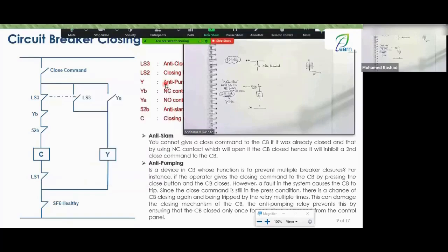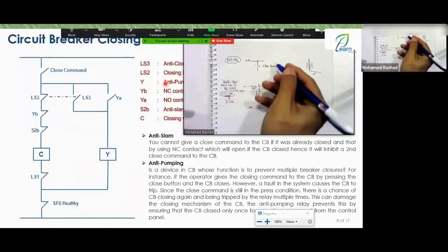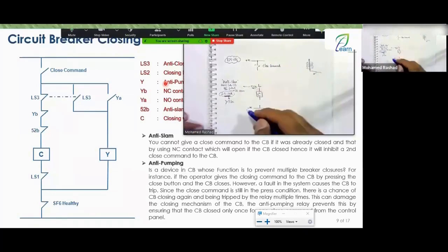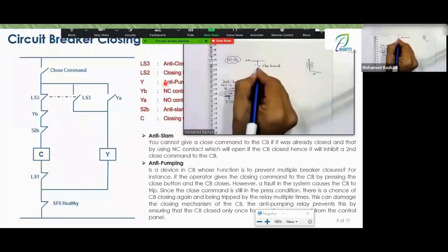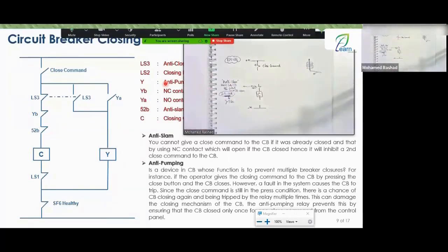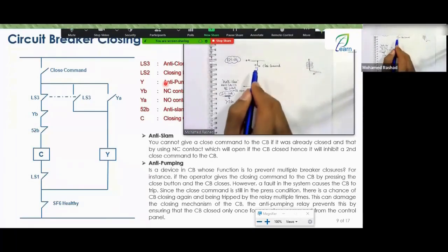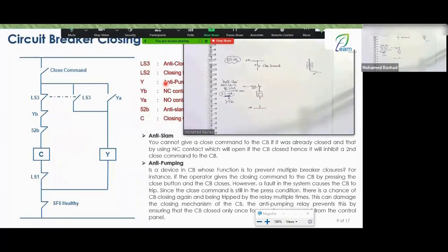All right, Engineer Fairs asks me, what are the reasons for the burnout of the closing coil other than the anti-slam? Okay, I'm about to discuss that. So the first, anti-slam is made so the closing coil doesn't burn, by ensuring that you can't give another close command if the breaker is already closed. All right, great. So the breaker was open, I gave it a close command, and the DC reached the closing coil. All right, the breaker closed and I'm about to continue discussing this.